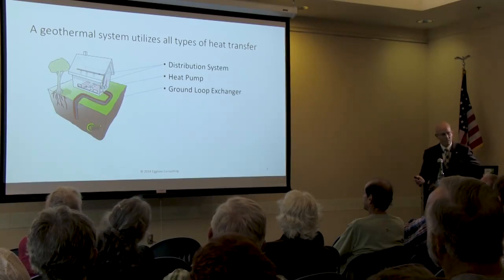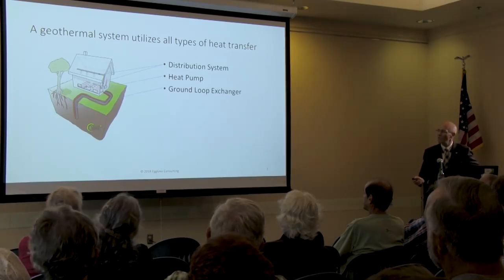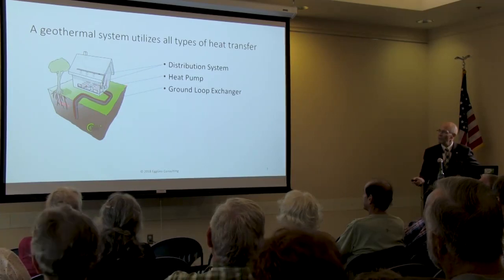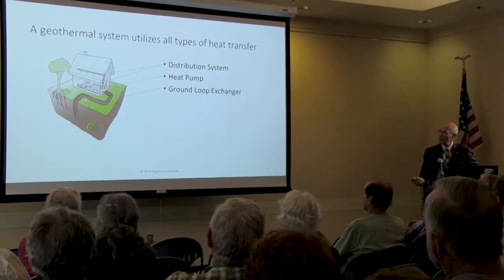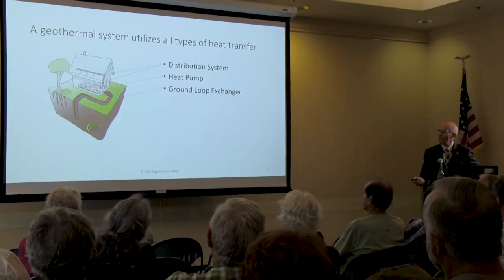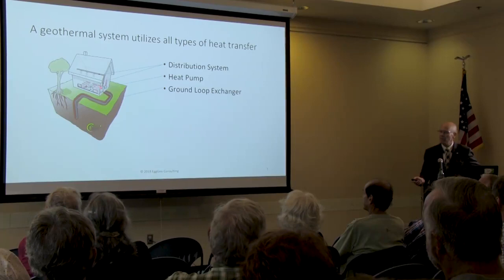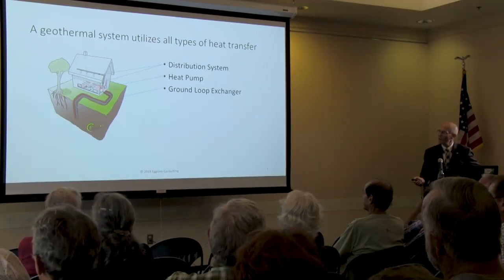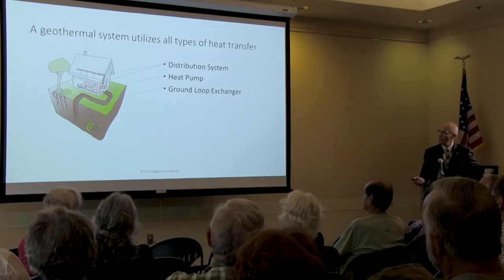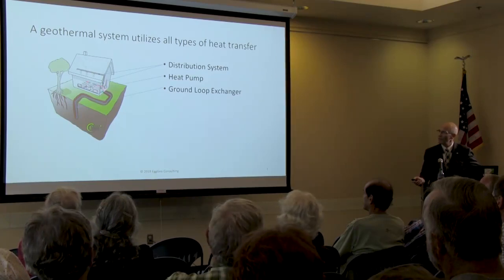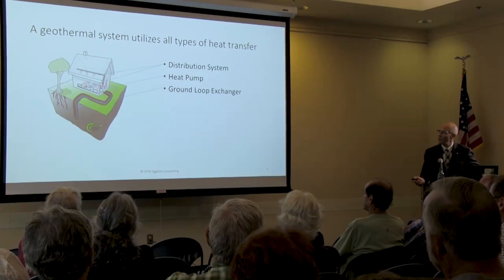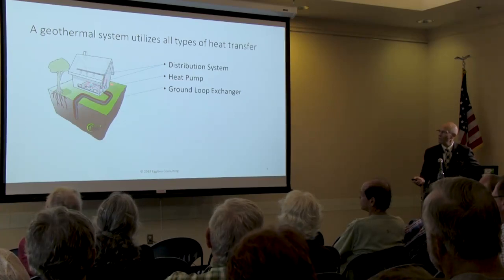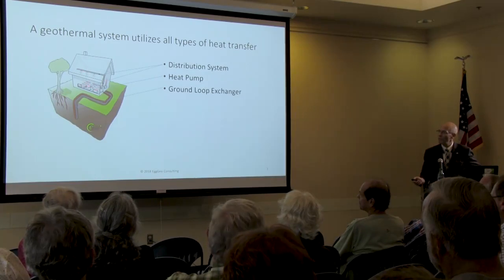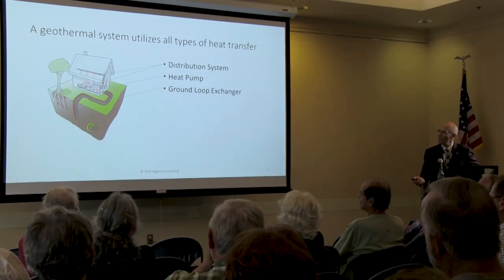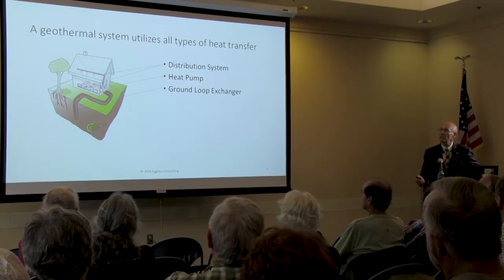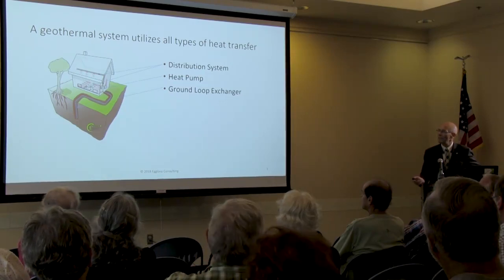In every geothermal system of which I'm aware, there are a few exceptions to this, and we'll talk about them, you have at least a ground loop exchanger of some sort, and there are many kinds. You have a heat pump, which is usually a device that runs on the Carnot refrigeration cycle, and because it manipulates heat, it compresses heat to help the thermodynamic process. And then you have a distribution system. The distribution system can be forced air, or it can be radiant, or a couple of other potential ways. Like in here, we have a forced air system. You can feel the air coming from the ceiling.